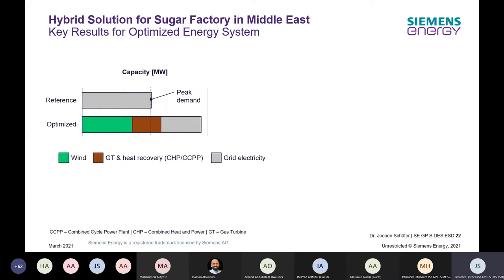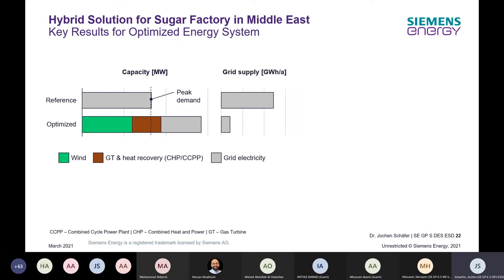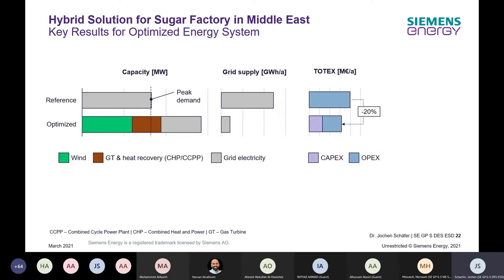In the reference case there is a power draw from the grid with some peak demand. In the optimized case, we have a significant wind installation, a gas turbine with heat recovery, and still use grid electricity especially for peak demands — but significantly reduce grid energy intake overall. This grid energy reduction is why we save money, and the system shifts from a pure opex model to a mixed capex/opex system due to the investments made, with synergies in electricity and steam production delivering the 20% TOTEX reduction.